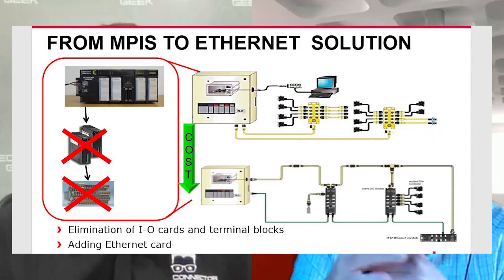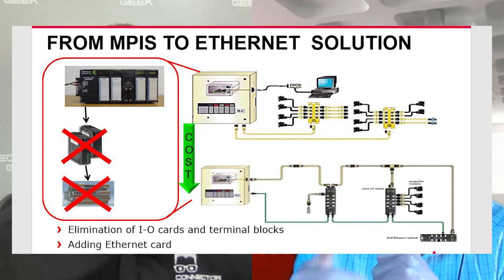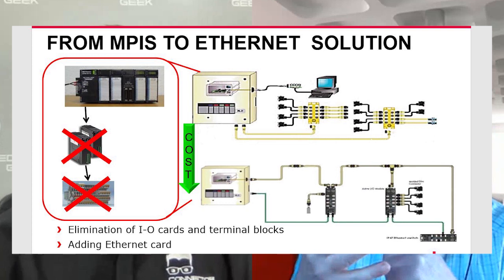And then what we're seeing more now is the approach into network-based systems. We have Ethernet IP, we have Profinet, the 2 main ones moving forwards. And that then brings the other block that you showed, which is the IO. So it's actually an active block. That takes all of those signals, all of that power, and brings it over an Ethernet-based system. We can have 256 of those blocks connected through one RJ45 connector in the cabinet. That's 256 times 8, actually 16, because we can double those up in those blocks as well, bringing 2 sensors into one port. So it's 4,096 connections through one RJ45, and then 5 connections for power.